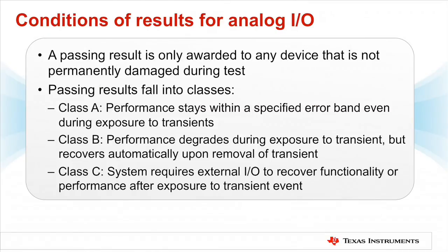Any system that is not permanently damaged from exposure to these tests receives a passing result. Units that do pass the test are awarded results that fall into various classes. Class A systems perform within a specified band, even while being exposed to the transient signals. Class B systems exhibit degraded performance during exposure to the transient, but recover automatically. Class C systems require external interaction to recover from exposure to the transient event.